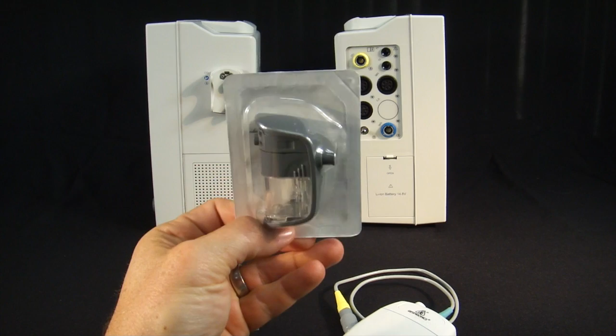These water traps are good for multiple patients for an extended duration of time. The machine will notify you when they've become full or occluded, and you simply replace them. These carry an end user cost of $25 to $30 depending on quantity, and again are good for many patients. So your overall patient cost is lower with the Edan G2 CO2. Also, your customer's initial expense is less, as the G2 CO2 module is less expensive. It is built into the side of the machine, as you can see. It's just above the printer port.